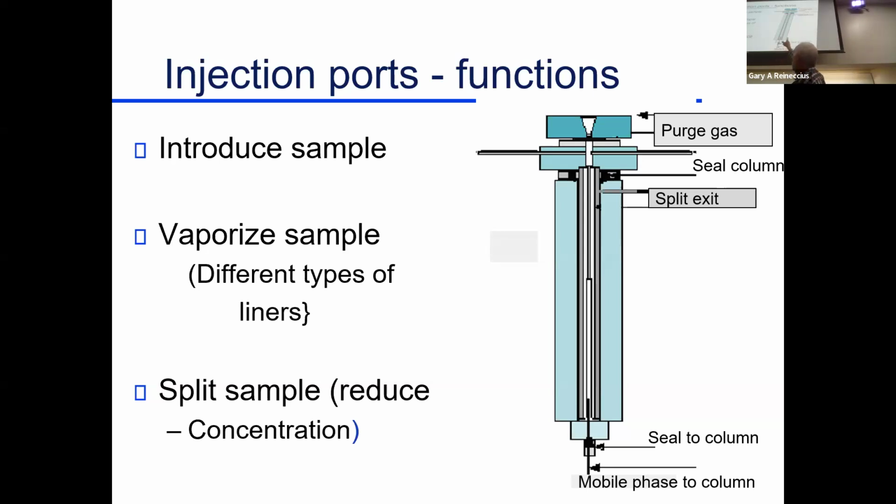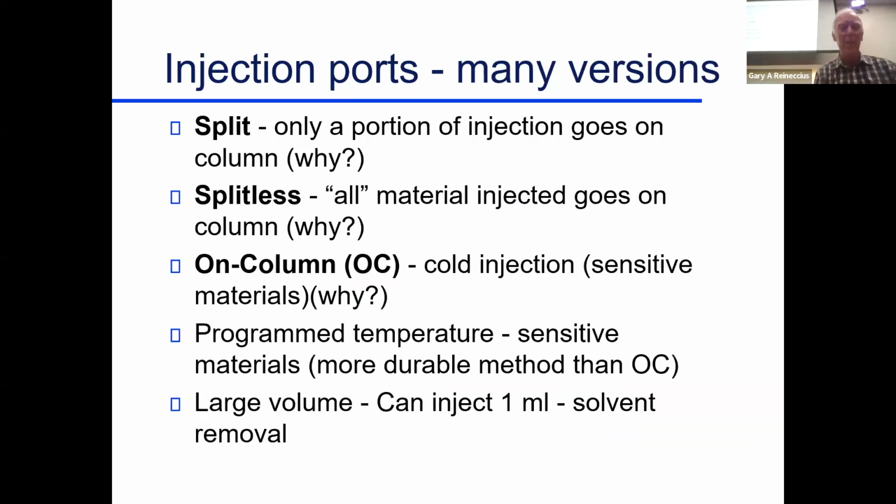And actually where you make your injection at the top going down, if you've got crud in there, it's not just your analytes you want to find, but you find you got a little bit of sugar, you got a little bit of protein, you got a little bit of something else in there. That also then gets charred in the middle, and you start building up garbage in the middle. And so anyway, this needs maintenance. It needs to be kept clean. It needs to be kept from leaking if you want to get decent results. So that's the injection port.